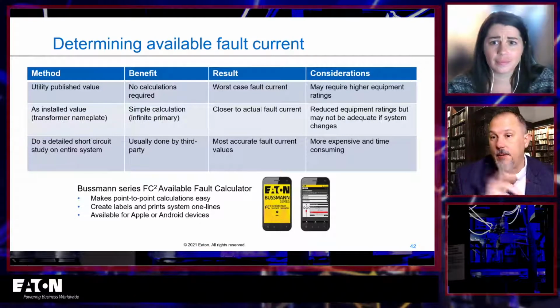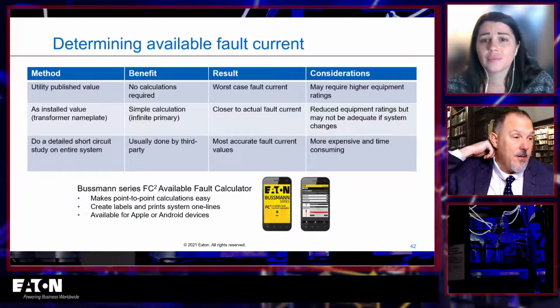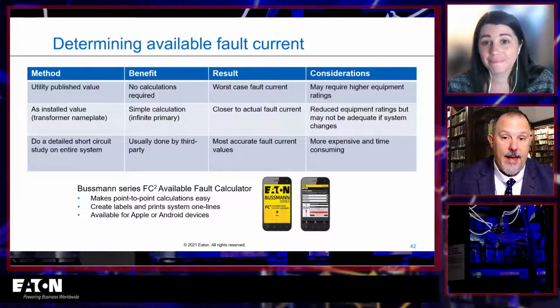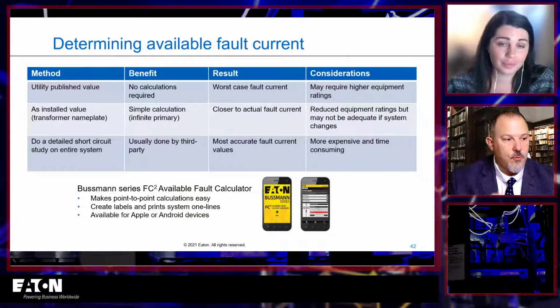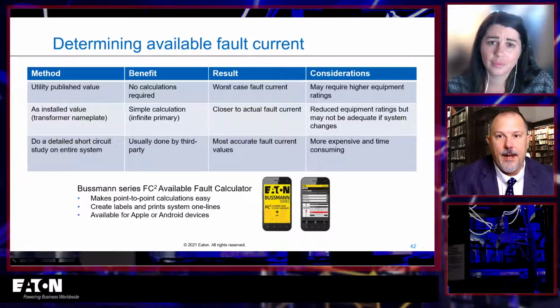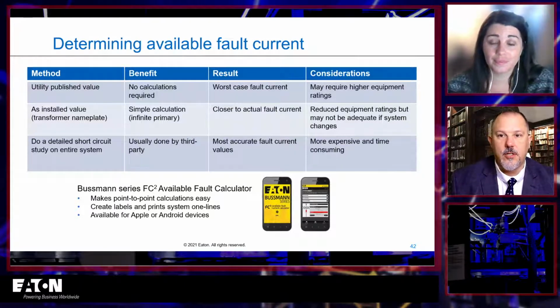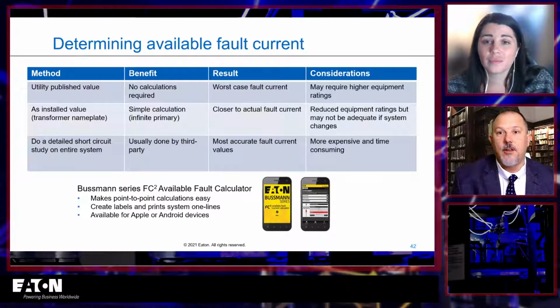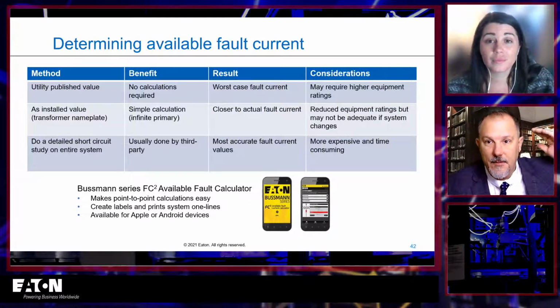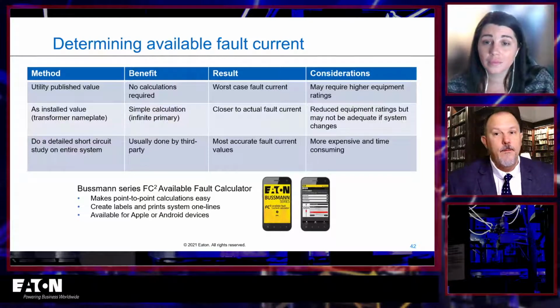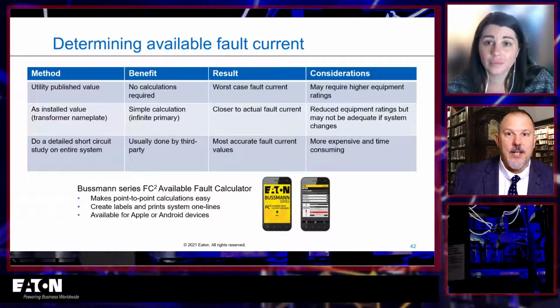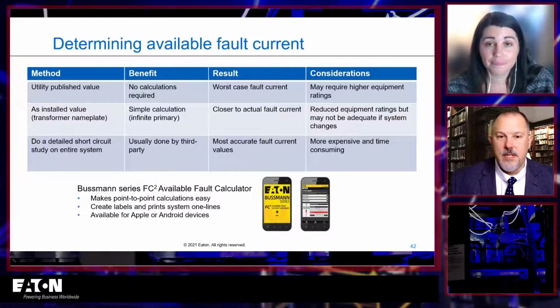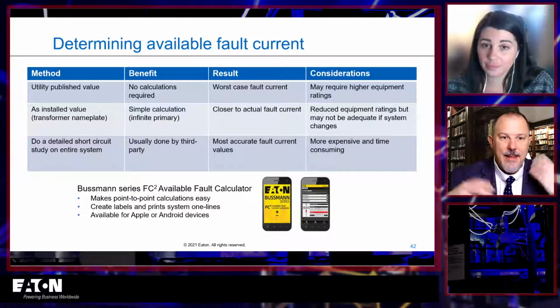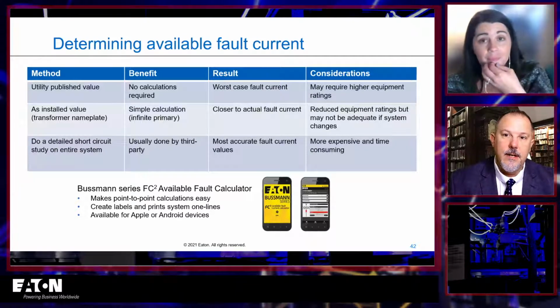And Joe Bellantoni is a fan. Most people I know, I mean, this is a very heavily used app, and what I like to do is just run some scenarios and play with it. You don't need to model the transformer. You can just say, look, I know what my fault current is at the front end of this conductor, and put a conductor length in, put a conductor size, number of conductors in parallel, and run those examples. They're great for classrooms. They're great for just getting that ballpark figure in your head.